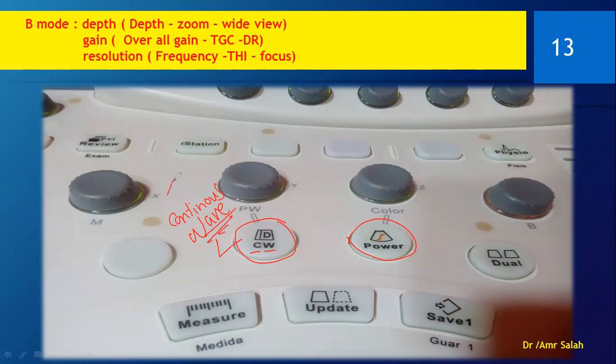The answer is no, we do not use it. It is used mainly by the echocardiographers. Should you find it activated, should you just leave it like this, or do you have to deactivate it? Yes, that's right, absolutely correct. You have to deactivate it before carrying on with the exam. Okay, so that's all for the CW.